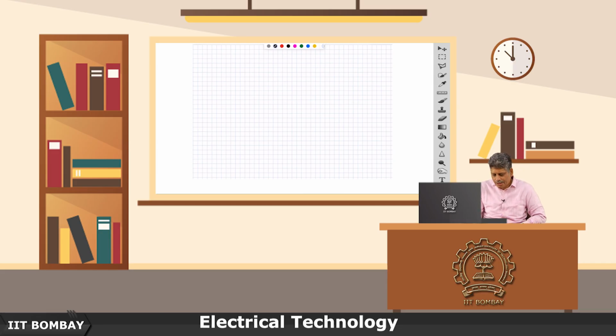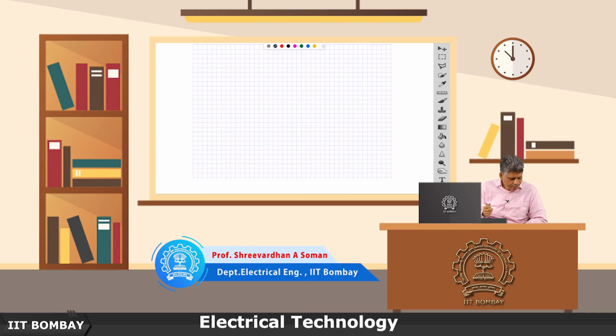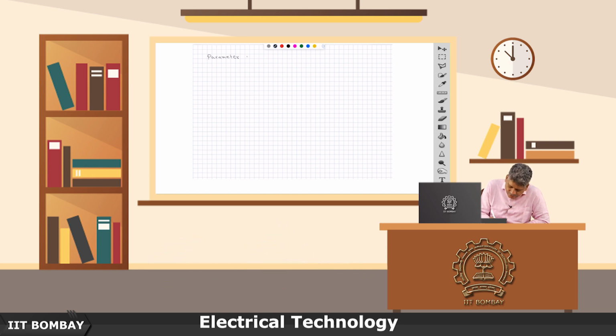Okay, welcome back. So, today I want to discuss the parameter determination of the induction motor's equivalent circuit. We want to estimate the parameters, but instead of saying estimation, I think the better word would be determination, because we are doing tests. Estimation usually means we are not sure, there may still be something unknown. We are actually doing tests and then directly measuring it.